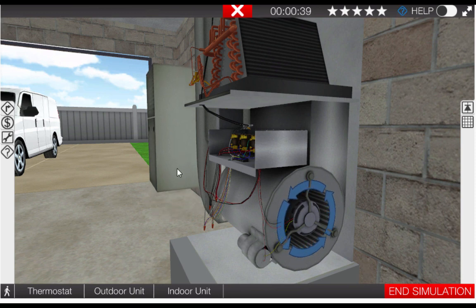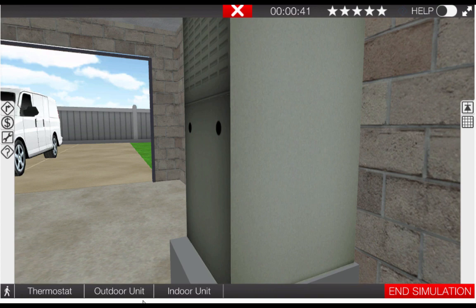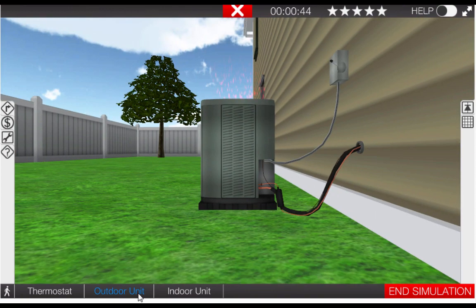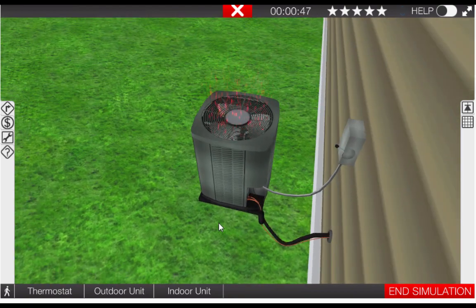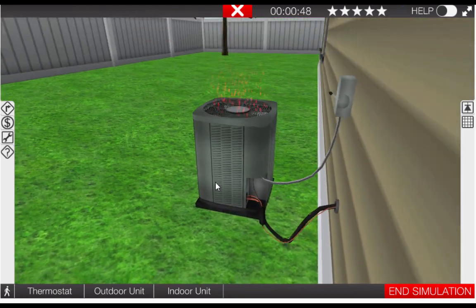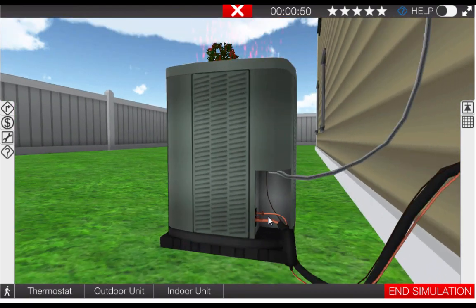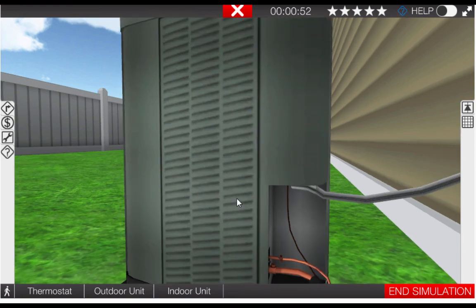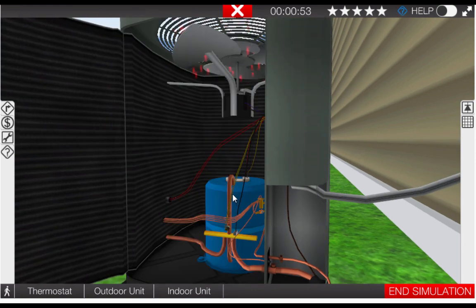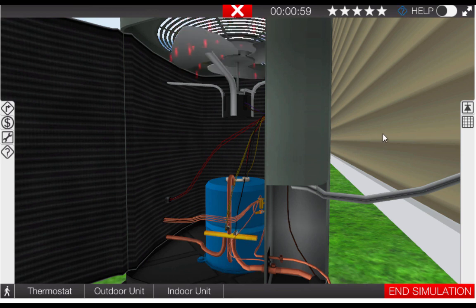Let's put the cover back on. Now we're going to go out to the outdoor unit and see if the outdoor fan motor and the compressor are running. We can see that the outdoor fan motor is in fact on and it sounds like the compressor is running too. You can always verify compressor operation with a clamp on ammeter if you can't in fact hear it.